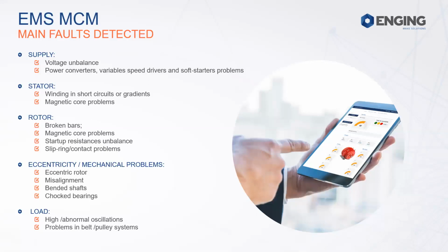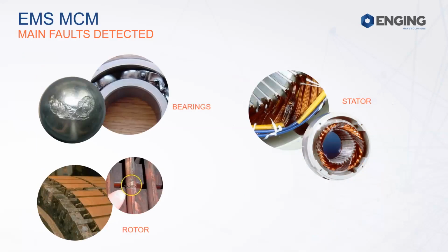In this case, we are able to pinpoint the fault, whether it is in the supply, in the stator, or in the rotor, entering the pure mechanical faults like eccentricity. We are able to reach the bearings, rotor misalignment, and also load problems, for instance in belts or pulley systems. We've applied these systems to paper industries.